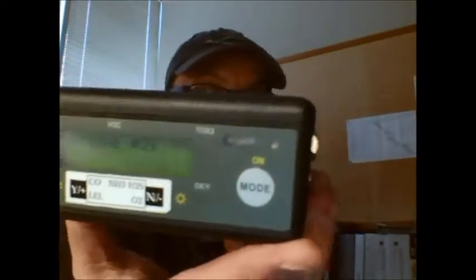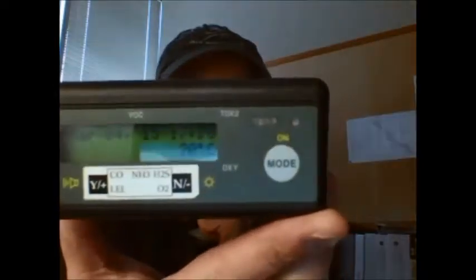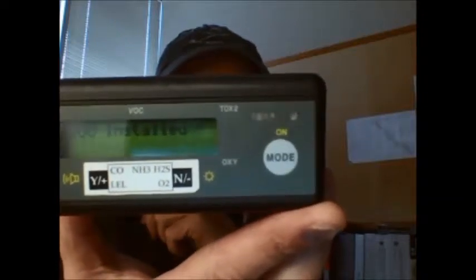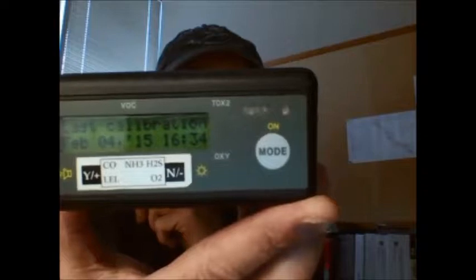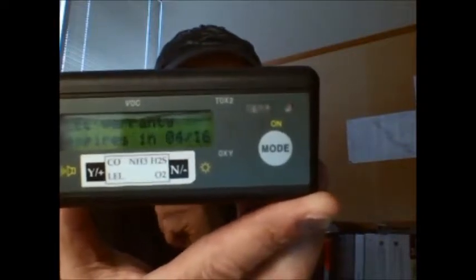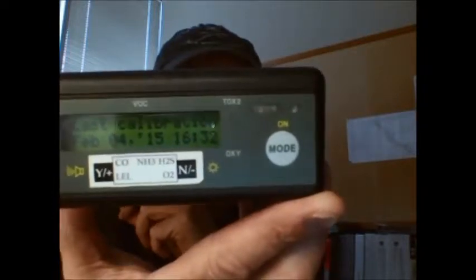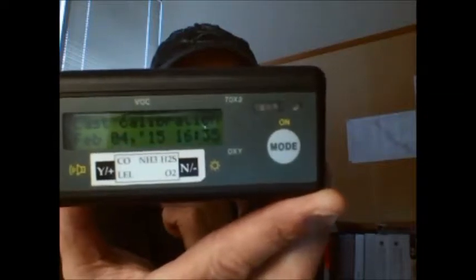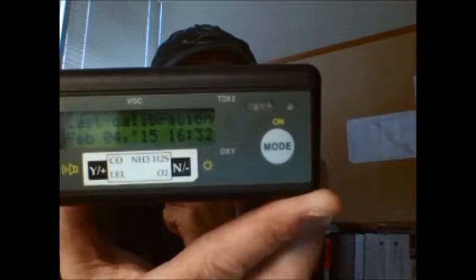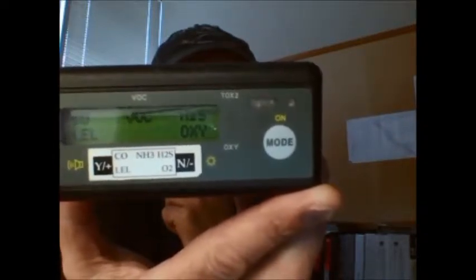So I'm going to turn on the detector right now. This is what it looks like. This is a MultiRAE multi-gas detector. So I will turn it on, because there's some information on here that you must view as it's turning on. And the pump comes on, as you can hear. It gives you dates. It's checking the sensor IDs. It tells you last calibration dates. It gives you the different cells and when their expiry is due. H2S. And there you have it.